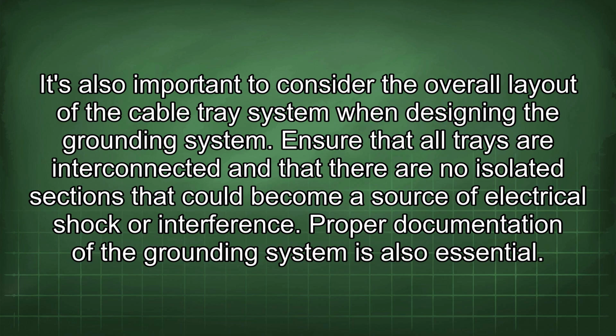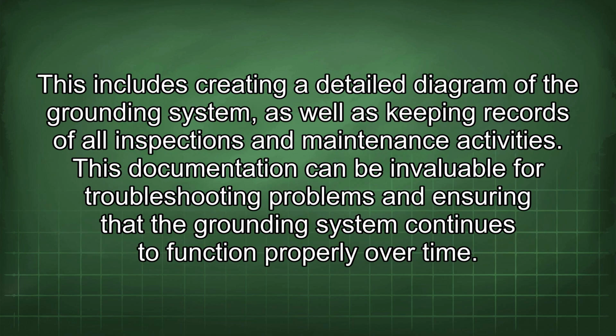Ensure that all trays are interconnected and that there are no isolated sections that could become a source of electrical shock or interference. Proper documentation of the grounding system is also essential. This includes creating a detailed diagram of the grounding system, as well as keeping records of all inspections and maintenance activities. This documentation can be invaluable for troubleshooting problems and ensuring that the grounding system continues to function properly over time.